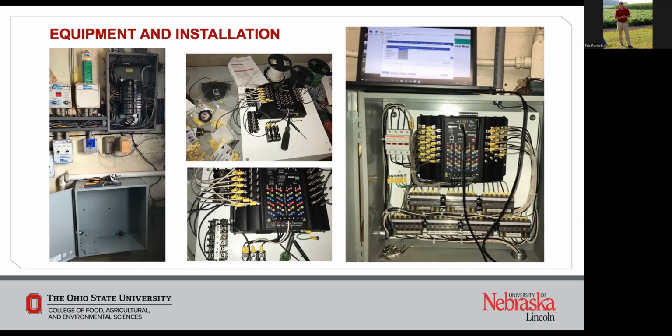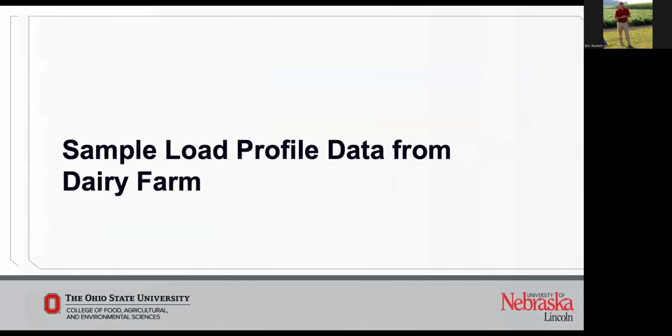And then of course we collect that data every several months. We'll go do a download. Our meters are configured to take data points every 5 minutes, so we're able to match that 15-minute rolling demand window. And we have a number of factors that we're collecting data on. We're getting interval energy, or your kilowatt hours, peak demand, so your kW, reactive kilovolt-amperes, kVARs, and power factor. So a lot of good data that we've been able to collect on these sites.